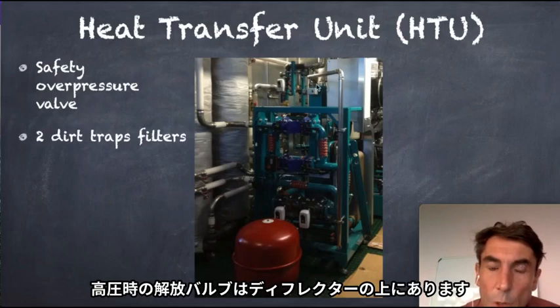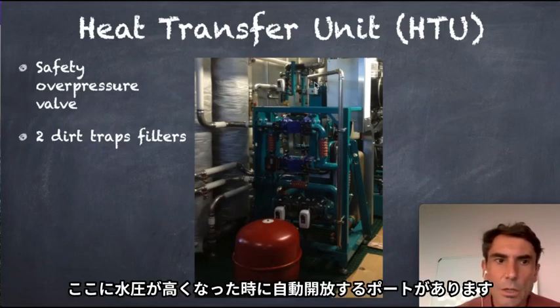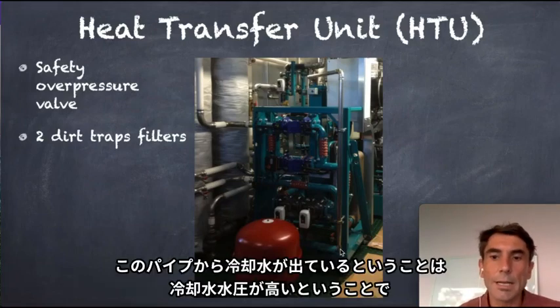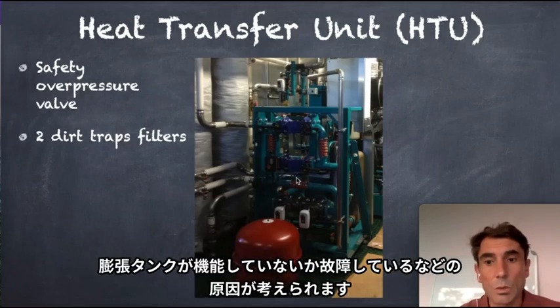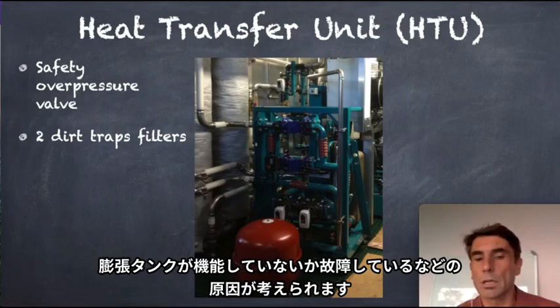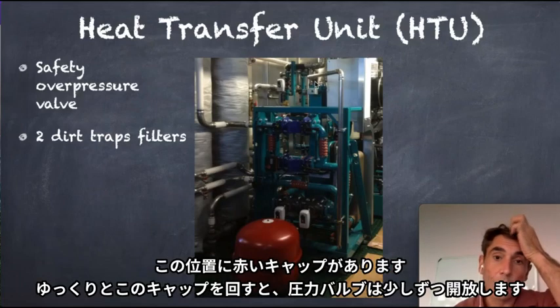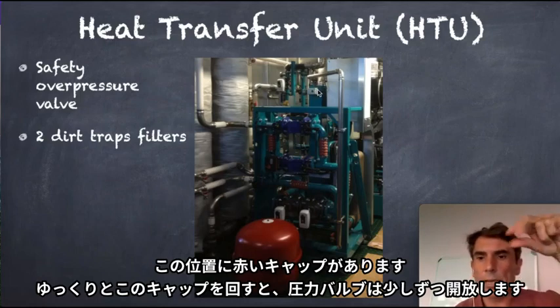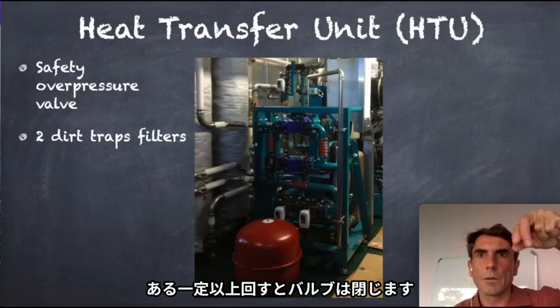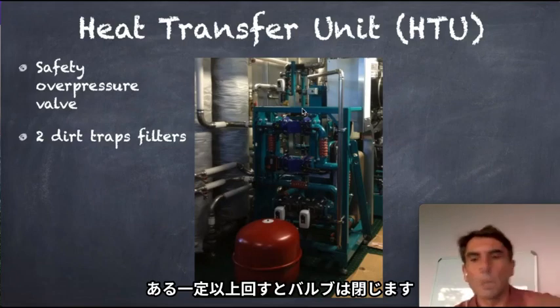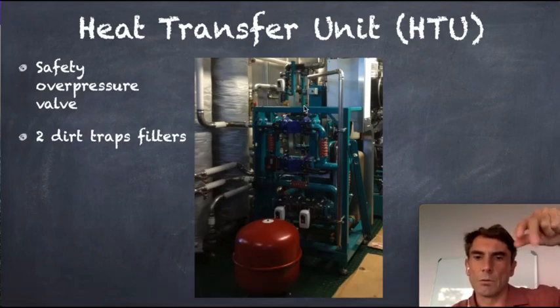So that's the pressure release valve on top of the hydraulic separator or deflector, depends on the naming. From here, if the pressure exceeds, the valve will open and release water and pressure through that pipe. So if this pipe is always leaking, then either we exceed the pressure in the system. So this could be a point that the expansion tank is broken or not working properly. So the pressure exceeds the maximum pressure of the pressure valve. Or if it's leaking, there's a red cap on it, and you can turn it. If you turn the cap, it starts slowly to open the valve. And then if you turn it wider, it gets over a point, and the valve will close immediately again. So it's like a spring valve where you can turn.